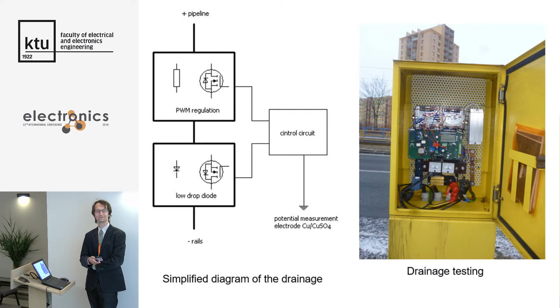We use PWM regulation, and PWM regulation causes harmonic components in current. In tramway it is no problem, because tramway uses no track circuits, but in railway there are usually track circuits which use some particular frequency, usually 50 Hz, 75 Hz, or 275 Hz. Any current which flows through rails must not interfere with these frequencies. This standard states some protective frequency bands for these frequencies, and states limits of current which can be injected into rails, or lower. The best is no current in this protective frequency band.